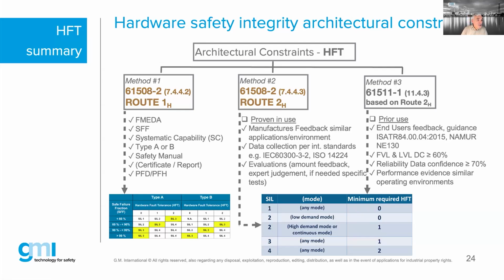Good. I got another question. If there is a transmitter fault, for example, 2 out of 2, one of the sensors is in error fault or taken into maintenance override, should the logic architecture adjust voting to 1 out of 1? That's a very valid and also a very good question.